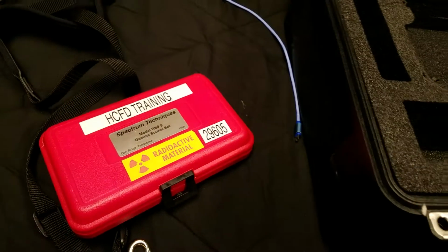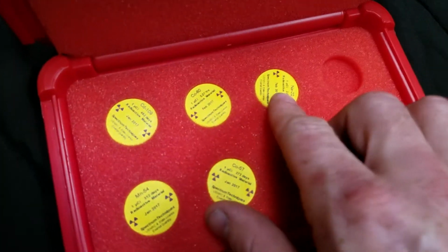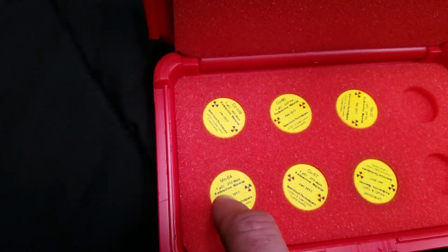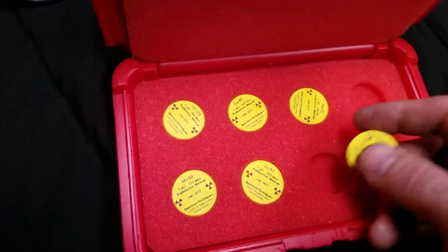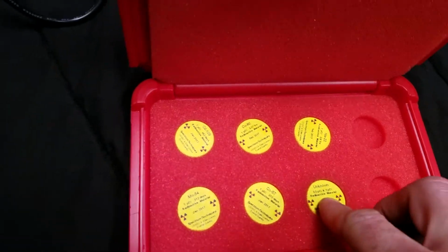I'm going to pull our machine away just to get our alarm to silence, and let's take a look at what we have in here. Looks like we've got cadmium 109, which it didn't even pick up, cobalt 60, which it got, sodium 22, which it did pick up. We had cobalt 57, which it picked up, manganese 54. And this is an unknown source, which looks like it has cesium 137 in it. So 2 of the 6 sources that are in there, this did not even pick up.